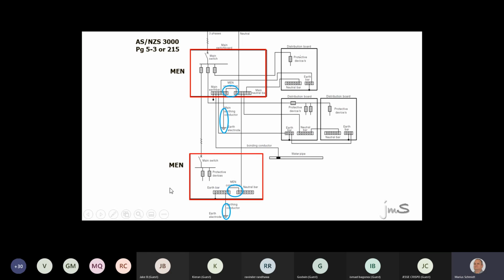But when do you have to install a switchboard in any building? When the current is 100 amps or more. So if you've got a house and a garage and they're separated, when do I have to put a switchboard in the garage? 3000 says if the current going to the garage is more than 100 amps. Otherwise, I can just run a TPS for the plugs and a TPS for the lights - it's just an extension of it.